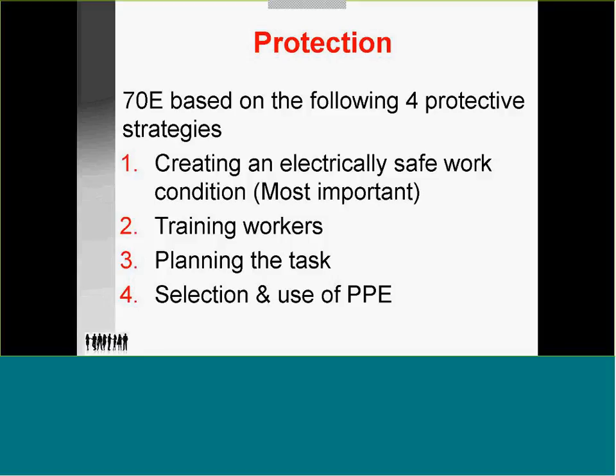Protection is based on 4 protect strategies. Create electrically safe work condition. Really, this is isolating what you're working on and de-energizing. Now, once you lock out, you must test for it. And unfortunately, yes, you must have the appropriate PPE on at the time until you can verify the absence of voltage. Once done, PPE is no longer required.